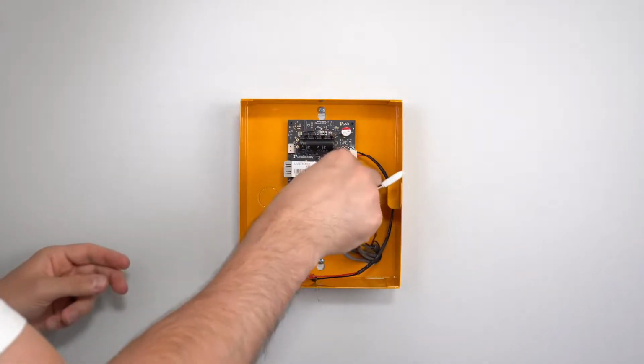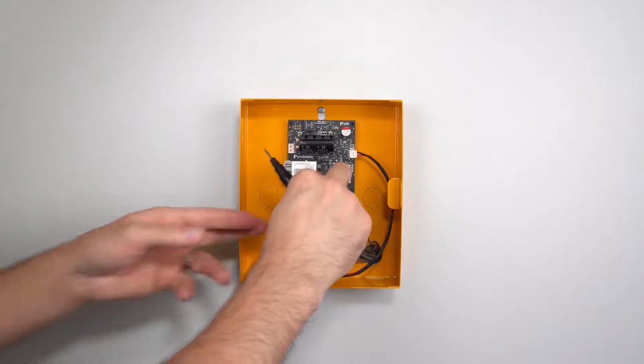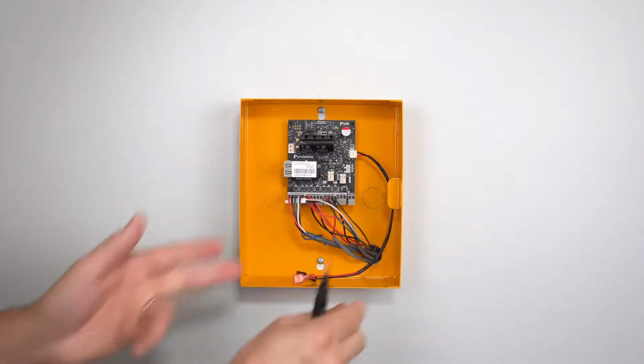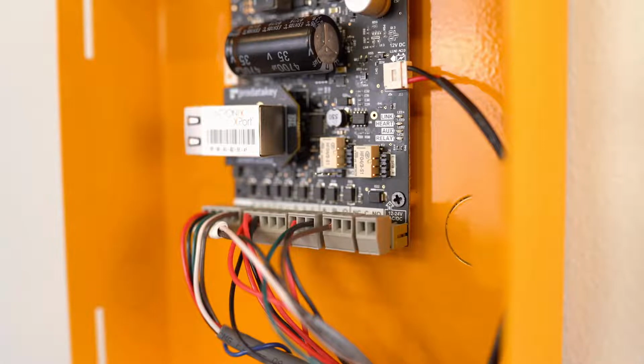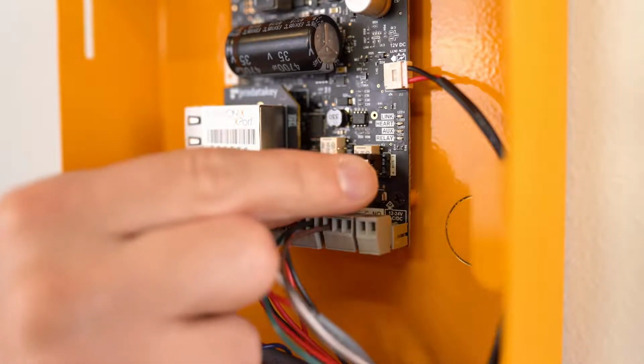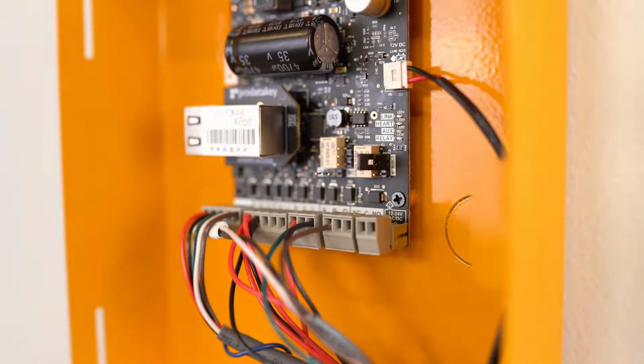In other words, if the Rex sees motion or the button is pressed, then it's going to cut ground to the maglock. If you trigger an allow on the controller, it's going to cut power to the maglock as well and open that up. The last thing that you saw in there was a little jumper. On our door controllers, we don't require that you bring negative or positive into the common on the controller itself. You can actually jumper positive or negative directly from board power onto the controller itself. So it's a really nice feature to save you a little bit of time as you're doing your wiring.